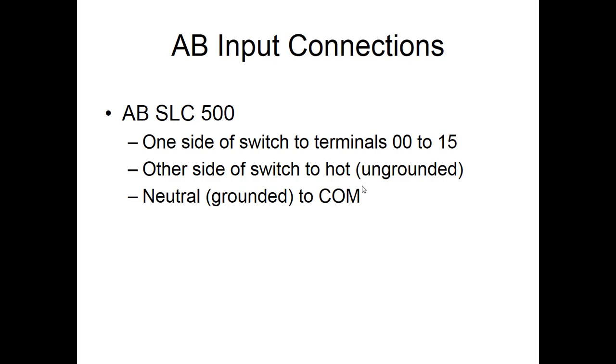On the SLC 500s, you'll be making connections. One side is connected to terminals 0 through 15. Remember, it starts at 0. So input 1, I guess, is on the 00, and it goes up to the 16, and that's number 15. And the other switch is hot. That's what we're talking about, the sourcing and the sinking. And then neutral grounded to COM. So that's going to be my connections.